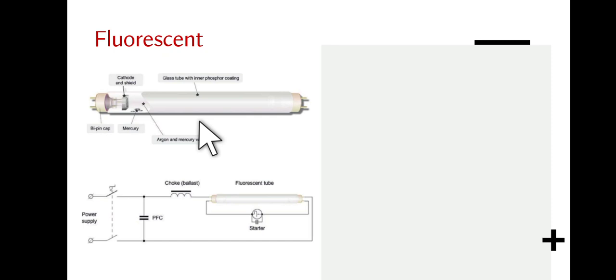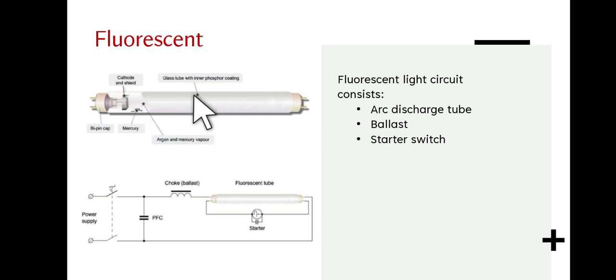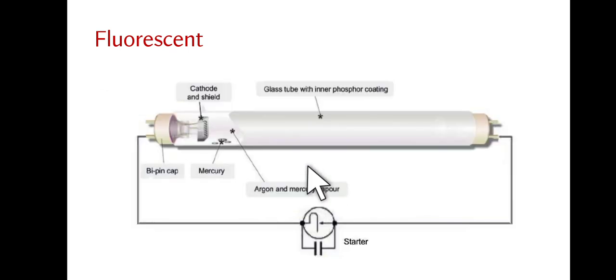A typical fluorescent light circuit consists of an arc discharge tube, a ballast, and a starter switch. The discharge tube has an internal phosphor coating and contains argon gas with a small amount of mercury. At the end of each discharge tube are electrodes known as cathodes.